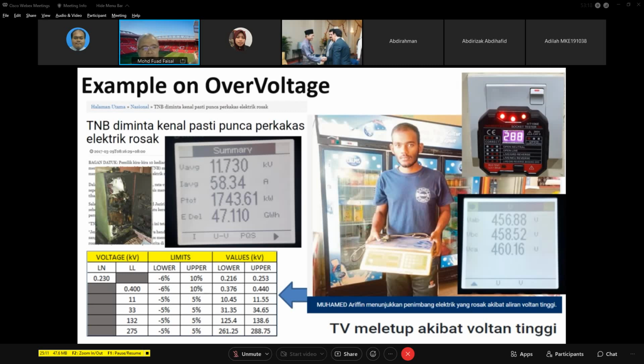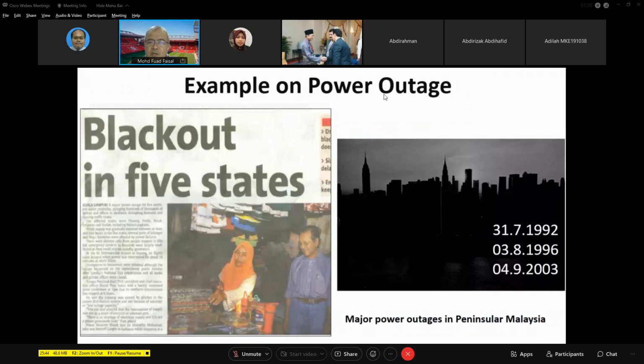And on the lower left-hand side of my slide, I'm sharing the same table of voltage limits. That's very important. So if you are experiencing voltage lower or higher than the limits, you must report to the utility. For Peninsular Malaysia, it will be Tenaga Nasional, but in Sabah, it must be Sabah Electricity Supply Board. If you're working in Sarawak, it must be Sarawak Electricity Board. Okay, next I'm showing the news clippings on outages. As mentioned, the famous, I would say infamous, outage in 96 in the Kedah area.